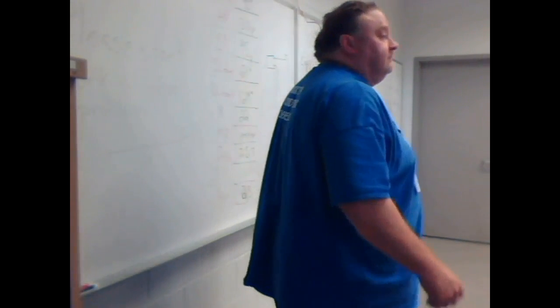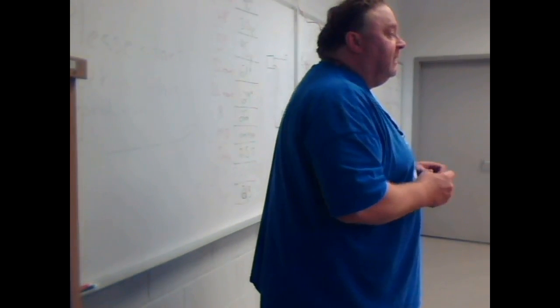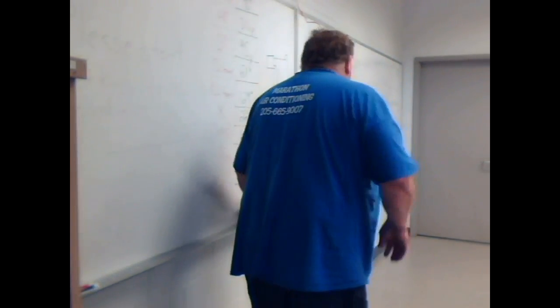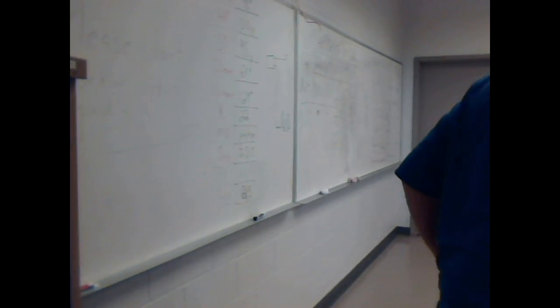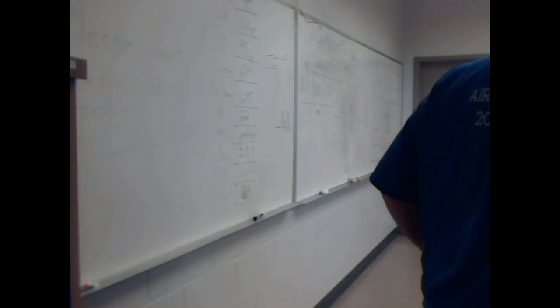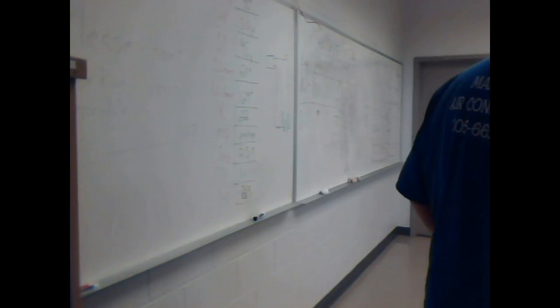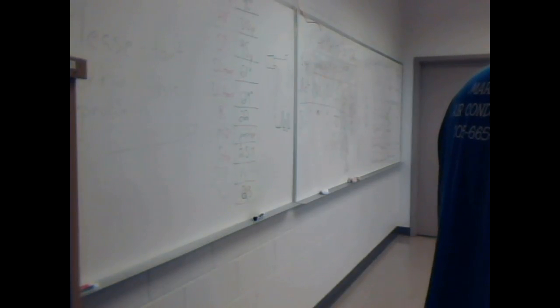Okay? Just proper design of the line. All right. So how far do you have to go up before you put the trap in? If it's going to be 10, 12 foot, I'm going to make sure I put a little trap in it. And it doesn't have to be separate pieces. I just take my line and make sure it goes up and then back down to trap. Okay, so that's on new stuff, right? You didn't put it in.